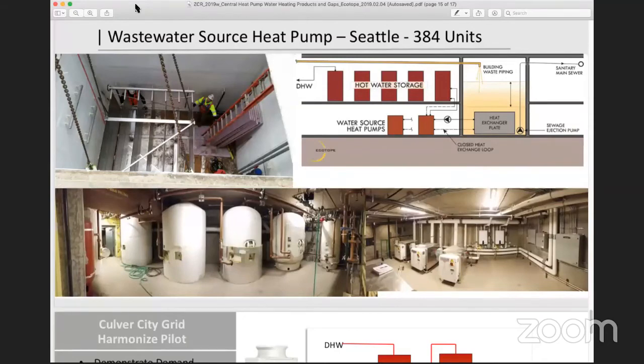We used to do a lot of drain water heat recovery, and we would see somewhere around 75, 80 degree entering water. If you were to go back and look at what that would do to the COP on that previous chart, you can see there is a little bit of a hit on that. So you'd have to balance that with how much you're getting off the drain water, and see if that COP hit was a function of dollars being stretched. You'd have to look at it - I just haven't done it. I usually would say, if you're going to invest in the heat pump, then no sense investing in the drain water heat recovery.